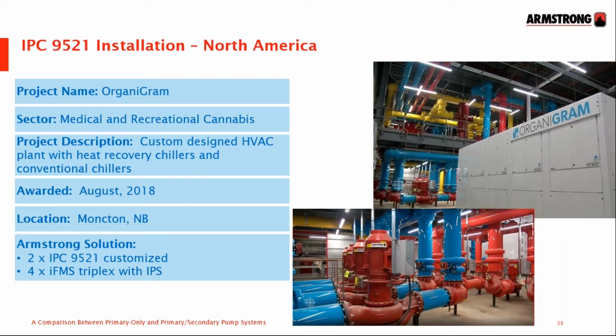The plant is one of the largest cooling projects in Moncton and one of the most unique, with the need for heating and cooling using both heat recovery chillers and normal chillers. It uses a combination of heat recovery chillers to pre-cool the chilled water return and then take waste heat from it for heating purposes. And the main chillers take the relay baton to complete the rest of the cooling. We've provided our design envelope IFMS, prefabricated pumping systems for the chiller plant, and 2 customized IPC 9521s offering chiller plant automation and optimization to work with this unique configuration.